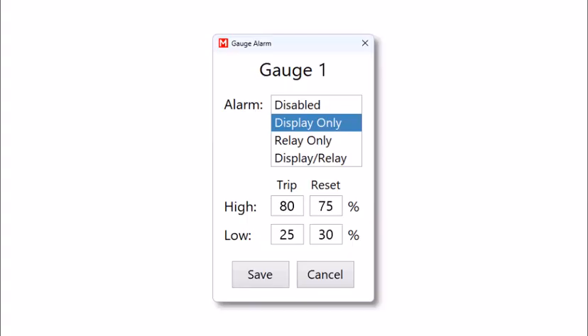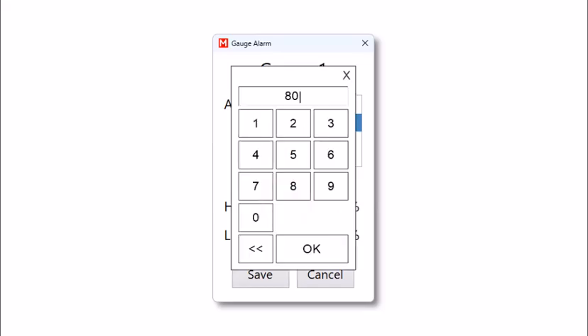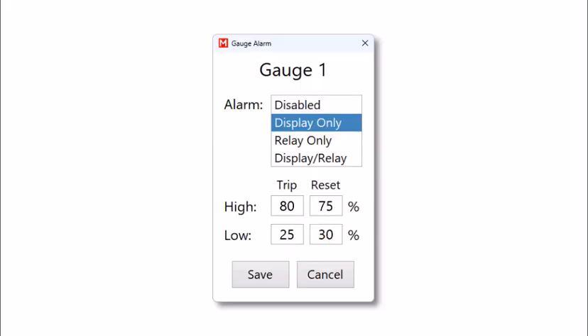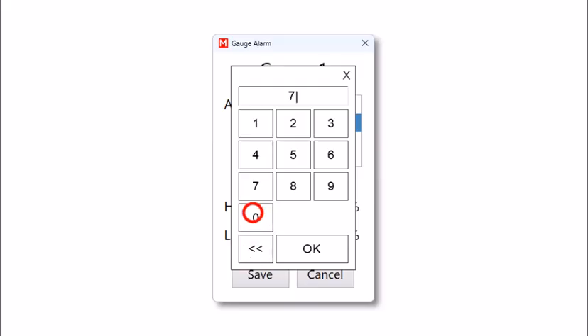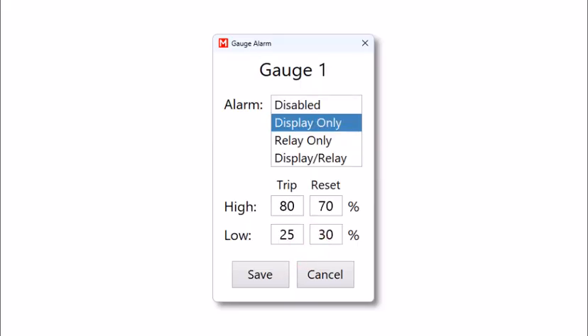Let's say we want to generate a high-level alarm when the bin is 80% full. To change that value, we would click on the high trip field, and that will open up a numeric input pad. We would type 80, then hit OK. That's the first half of setting up the high alarm. We also need to determine the point at which we want our alarms to reset. That will be the number to the right of the high field. Right now, we have our alarm triggering when the bin is 80% full with a reset level of 75%. That means that if the bin hits 80% full, the alarm will stay active until the level reaches 75%. If we change that number to 70, then hit OK, now the alarm will be active as long as the bin level is over 70%.